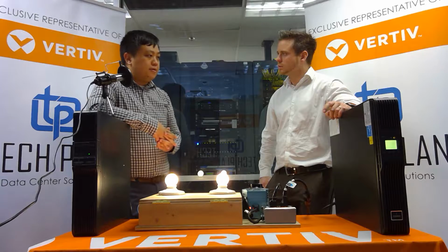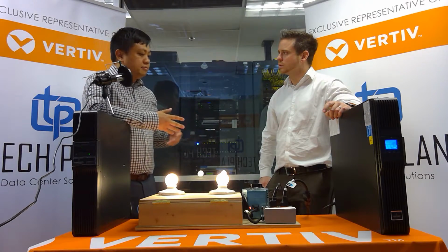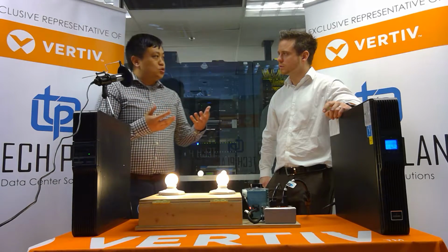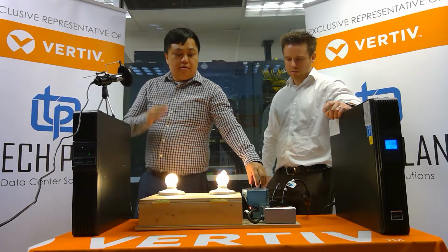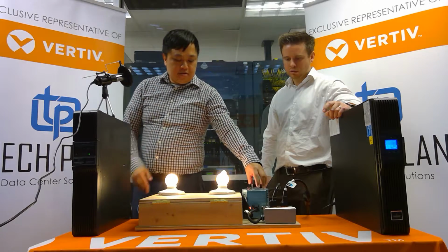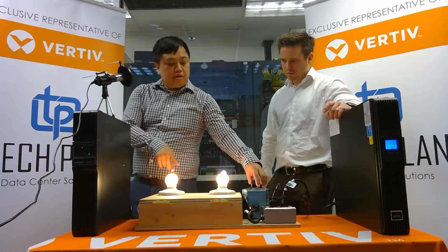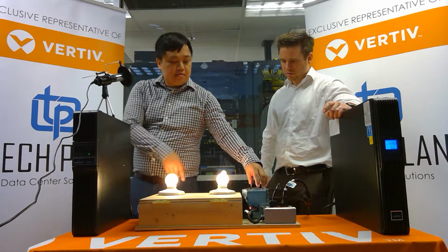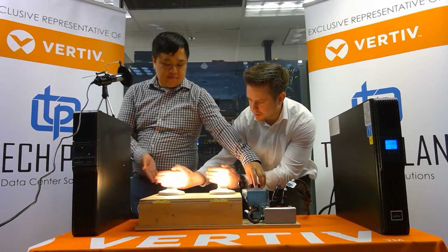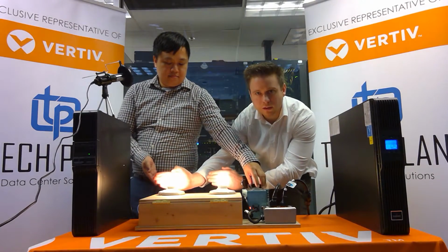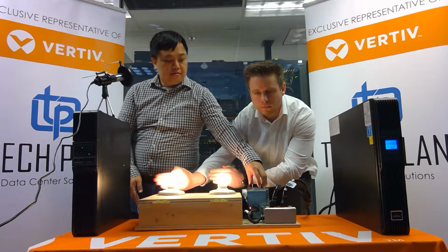Everything's back and qualified. Let's simulate some noise on the line. Let's just say there is a squirrel on the utility lines. Okay. So what you're going to see is a jump in voltage. And you'll see that actually does get translated to your load here with a line interactive style UPS, where online double conversion takes that all out. Let me just do this. You can really see the difference here. Yeah, because that is still connected to utility.